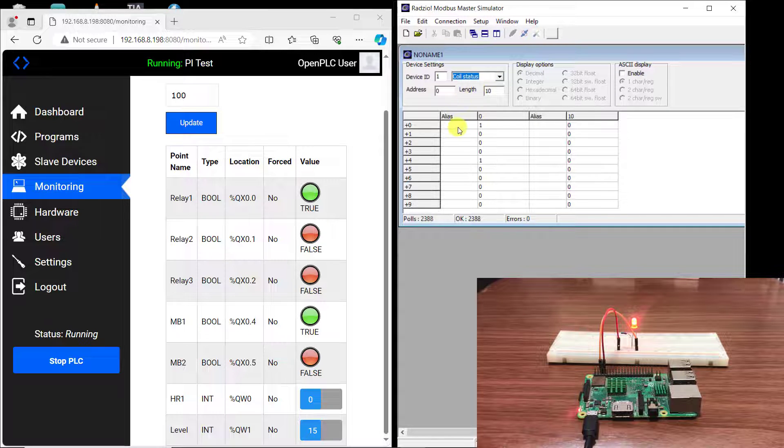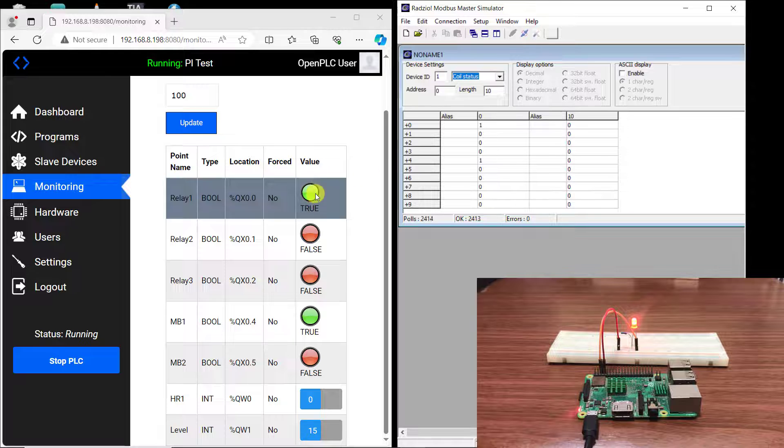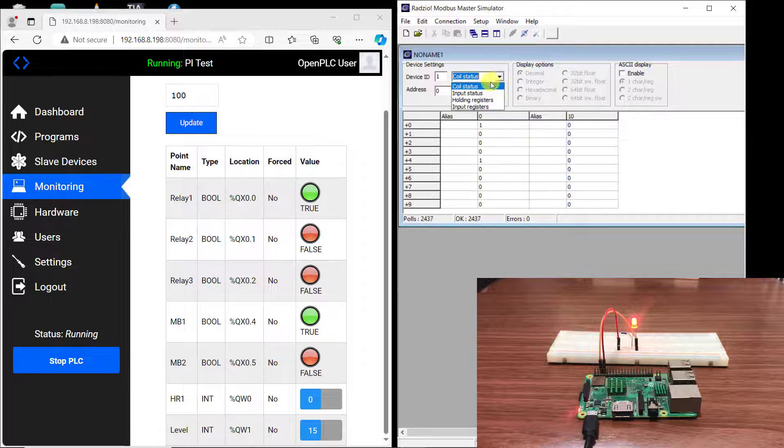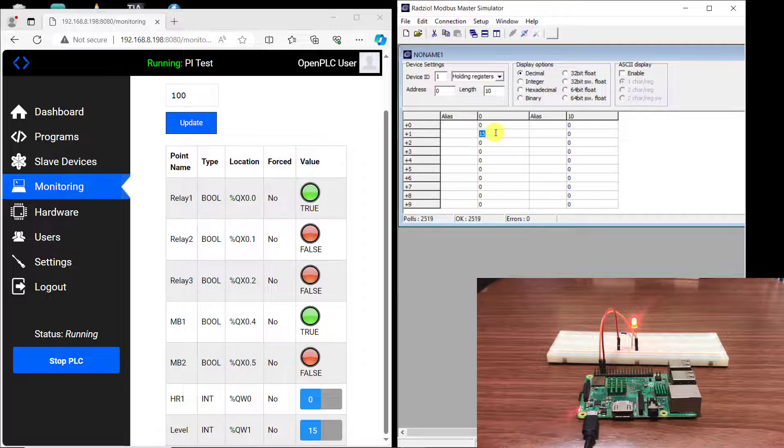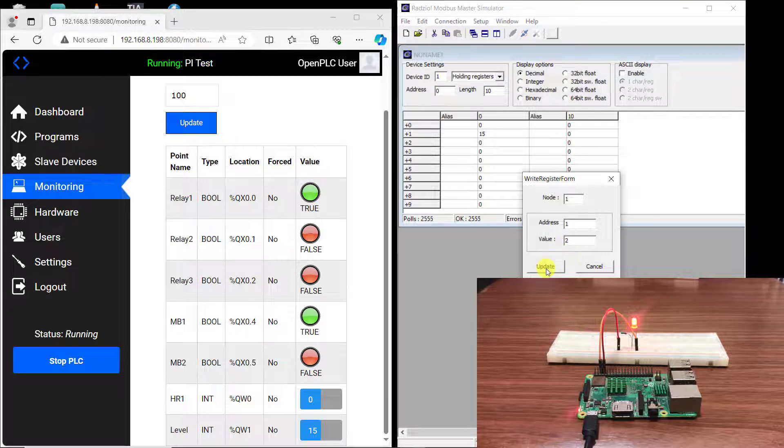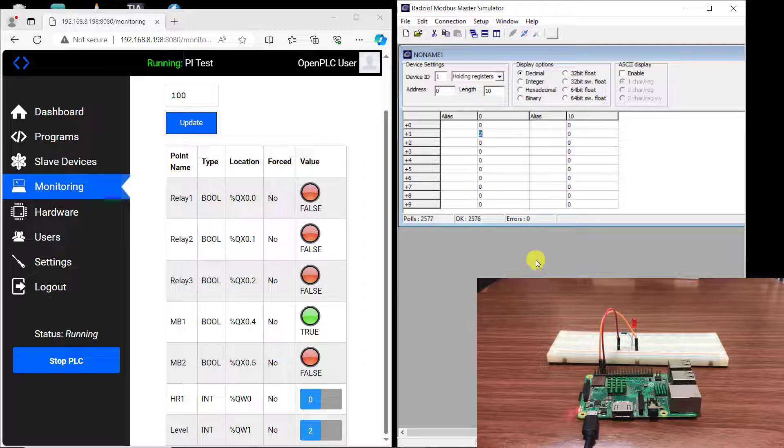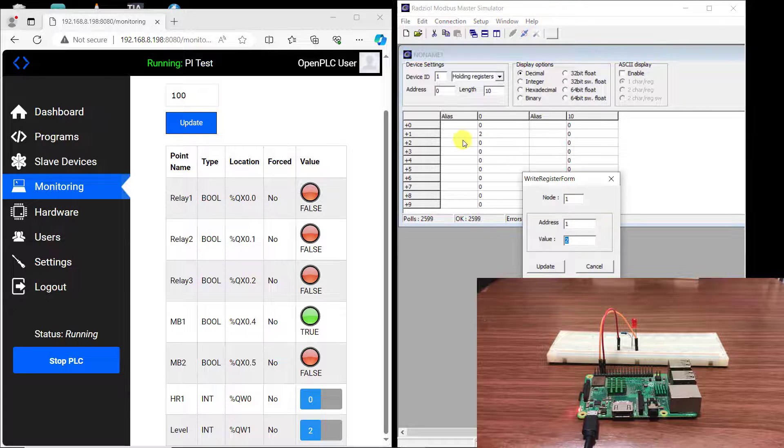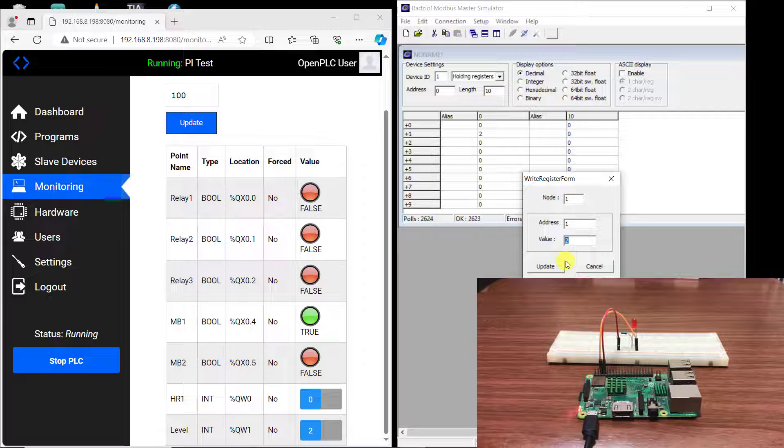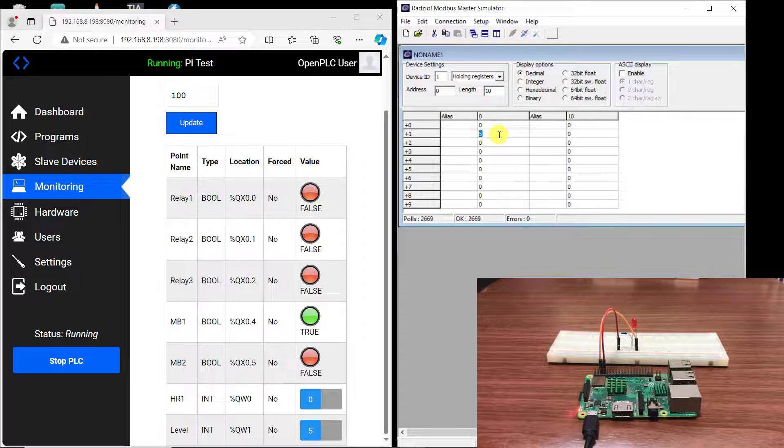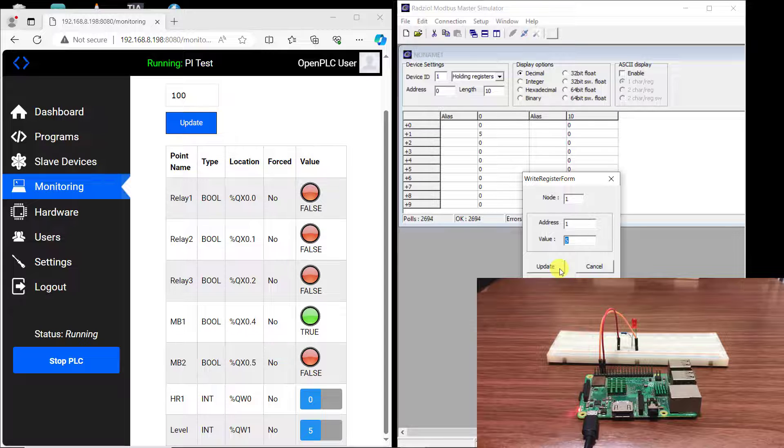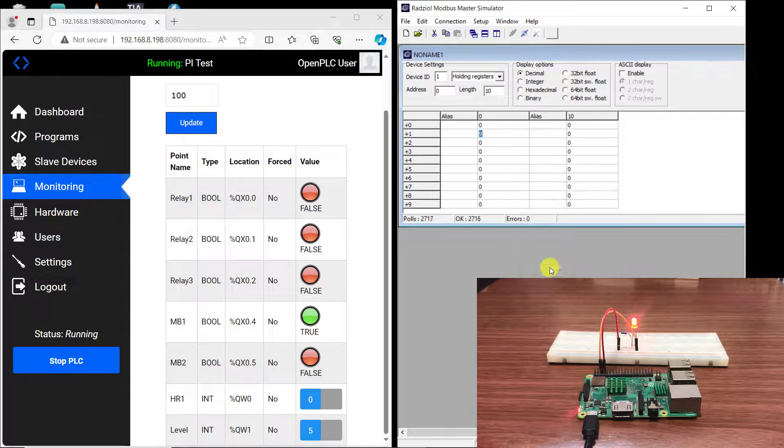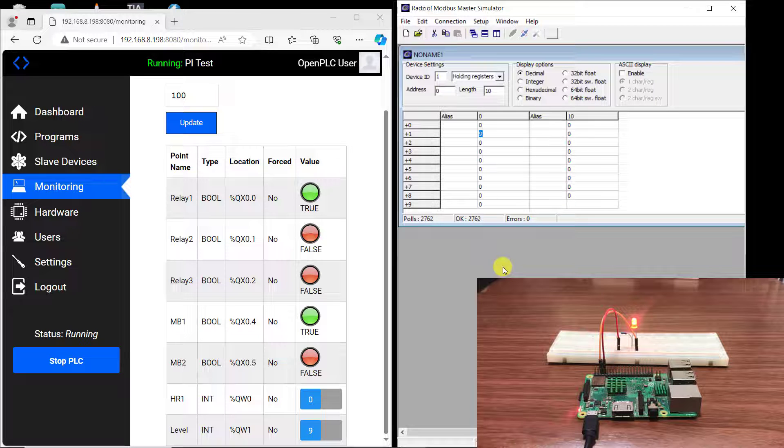And now move to the coil and then we can see that it is on also in the modbus master. I switch back to the holding register and then change this value to 2 and then we can see that the LED is off indicating that the pump is off, working perfectly. And now send it to 5. We can see nothing happened because it is less than 8. And then send it to 9 and then it comes back on again. Working perfectly.